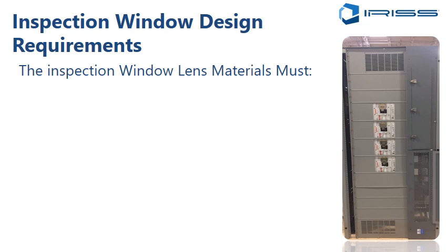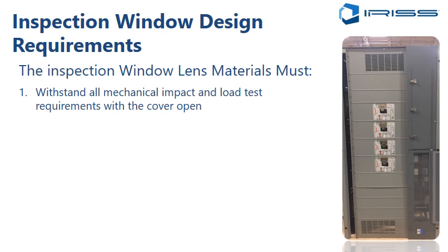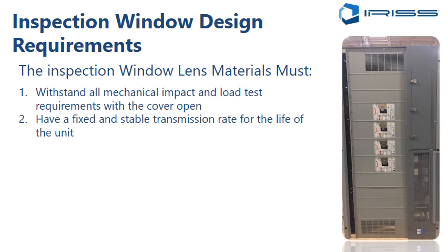The other things you've got to look at is the lens materials. They should be able to withstand mechanical impact and load test requirements with the cover open. So the cover should be open when you're doing an impact and load test. They should have a fixed and stable transmission rate for the life of the unit. Some of the fluoride crystals will degrade over time. So the polymer based crystals we find are much more stable. They don't lose transmission over time and are a far better option for the long-term viability of the system.